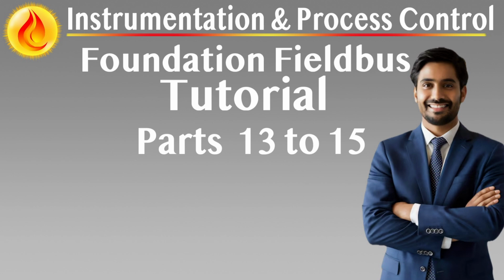Proper planning requires a holistic approach that integrates process requirements, instrumentation strategy, control system architecture, communication infrastructure, and lifecycle support. Unlike traditional 4-20 mA systems, Foundation Fieldbus introduces distributed intelligence, shared media, and deterministic communication, factors that must be explicitly addressed during project definition and front-end engineering design, FEED.